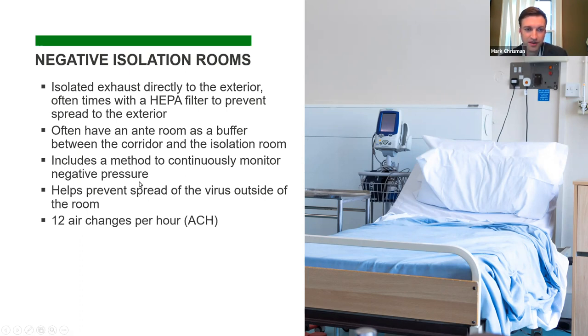Typically, in the short term, you could use something as simple as a ball in a wall that would tell you whether the room is negatively pressurized or not. But most hospitals have some sort of continuous monitor regulating the pressure in the ante room as well as the actual patient room itself. Because it's negative pressure, we're trying to help prevent the spread of virus outside that room. To classify as a negative airborne isolation room, we have to get 12 air changes an hour, which is quite a bit.